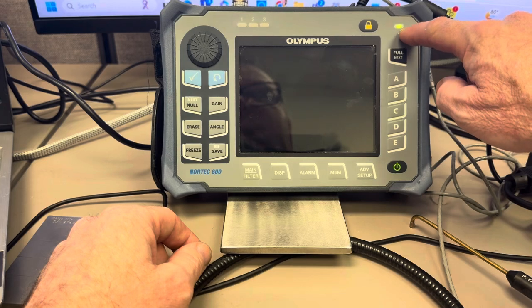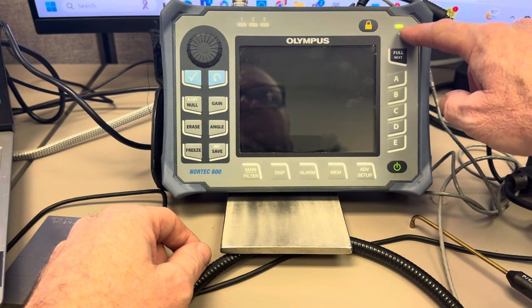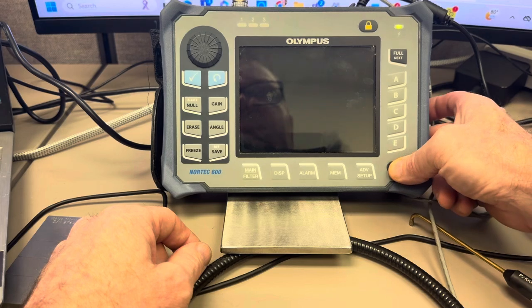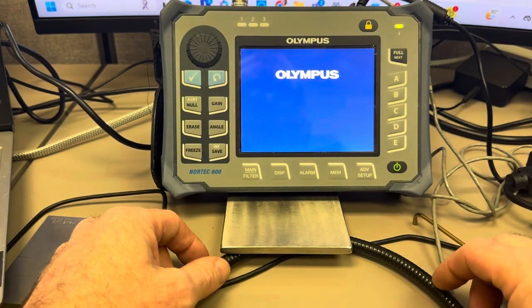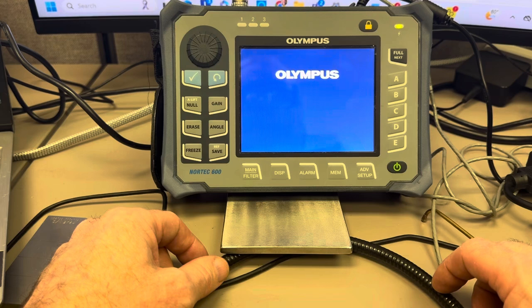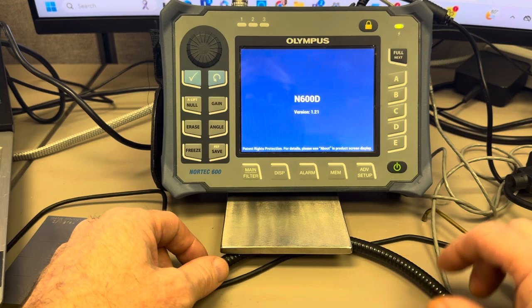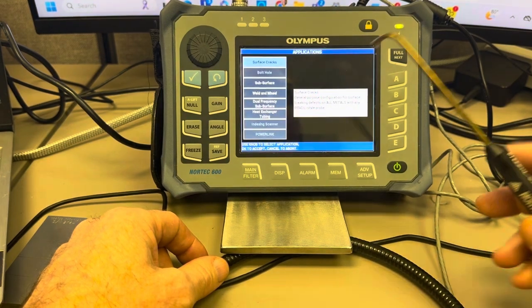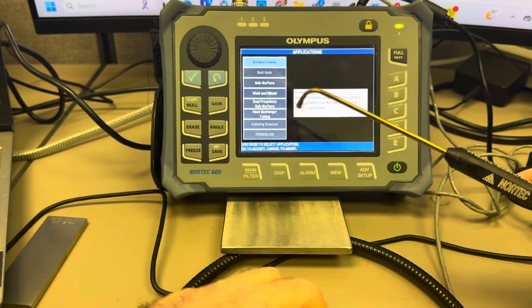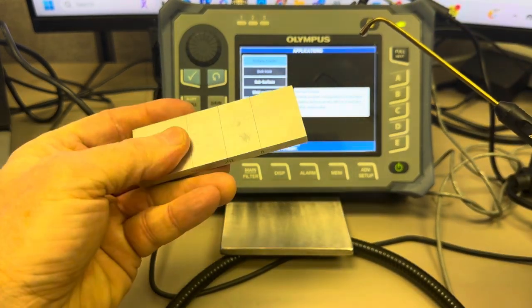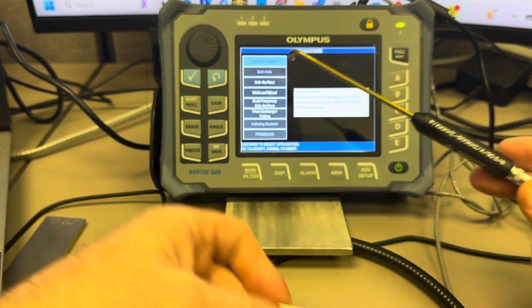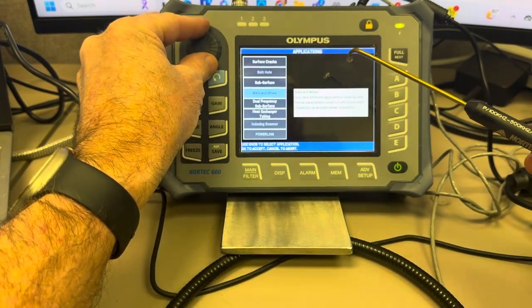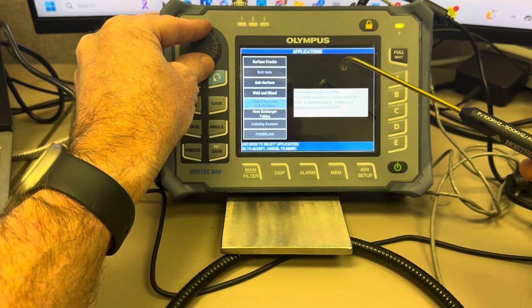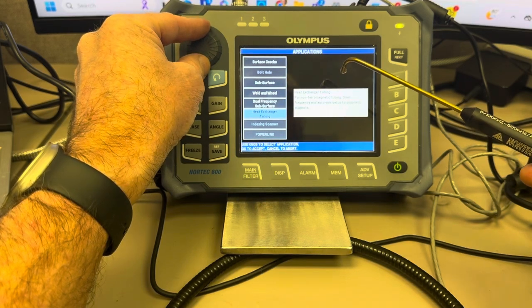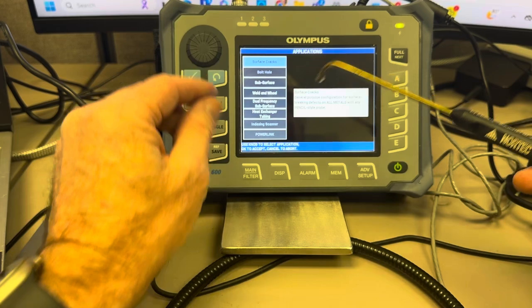Charging indicator shows my battery's good. It's been plugged in for a while. And of course our power button. Let's test that one out first. So we're going to watch the test instrument boot up. Now when it completes its boot up sequence, it's going to be asking us what type of test we want to perform. I'm going to be doing surface cracks, and I have an aluminum EDM notch block here. And I can select between subsurface, weld and wheel, dual frequency subsurface, or heat exchanger tubing. But I'm going to do surface cracks right there.